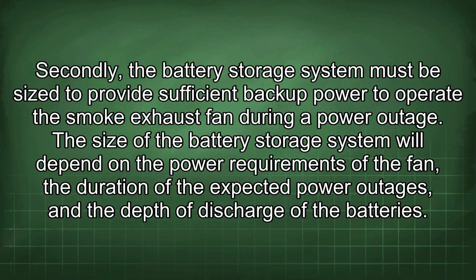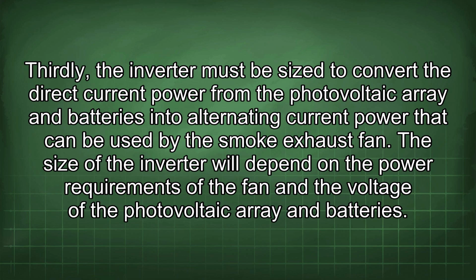Secondly, the battery storage system must be sized to provide sufficient backup power to operate the smoke exhaust fan during a power outage. The size of the battery storage system will depend on the power requirements of the fan, the duration of the expected power outages, and the depth of discharge of the batteries. Thirdly, the inverter must be sized to convert the direct current power from the photovoltaic array and batteries into alternating current power that can be used by the smoke exhaust fan.